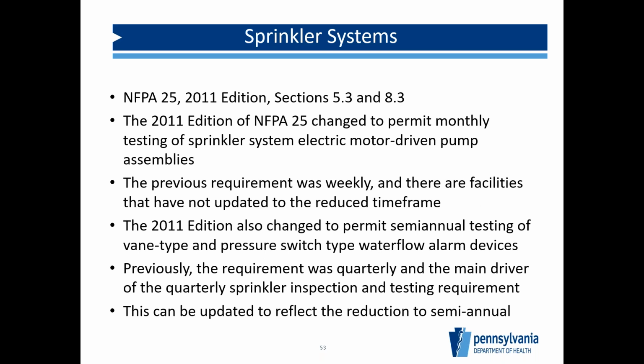So speaking of a sprinkler system, there was a change in NFPA 25 that some people aren't aware of, so I want to briefly go over that. It depends on what your sprinkler system is, so you might have to go back and check whether you have this, but that's why it's on the slide. Your electric motor-driven pump assembly: sometimes you don't have enough water pressure and you need some type of pump to push the water through your sprinkler system to get the proper pressures. The previous requirement was that they had to be inspected weekly, but now that is monthly. So if you have electric motor-driven pumps for your sprinkler system and you're still checking those weekly, you can push that out to monthly if you'd like. We're not going to complain if you keep it weekly, but it is something that you can change to reflect the change in the code.